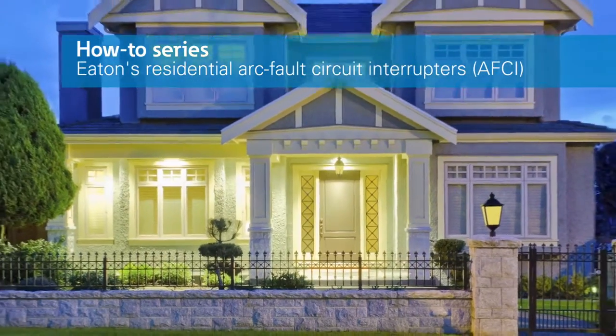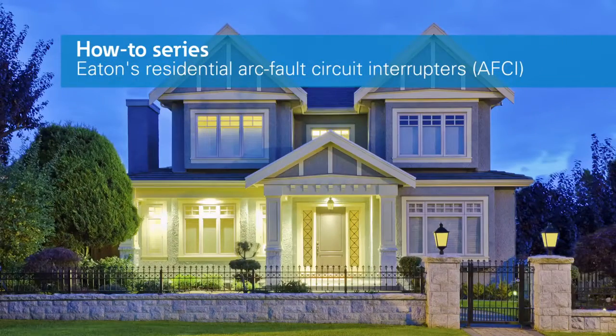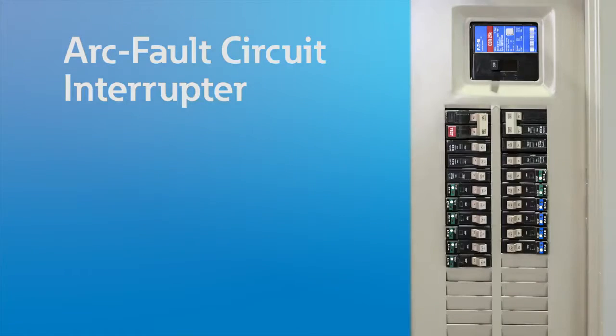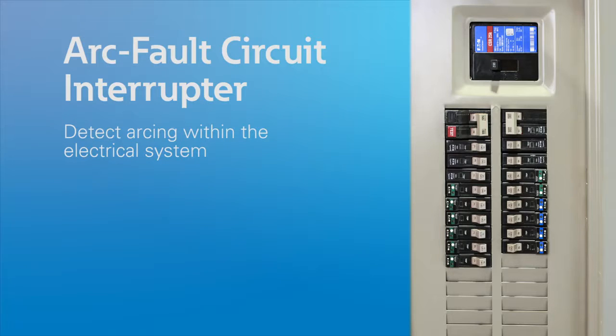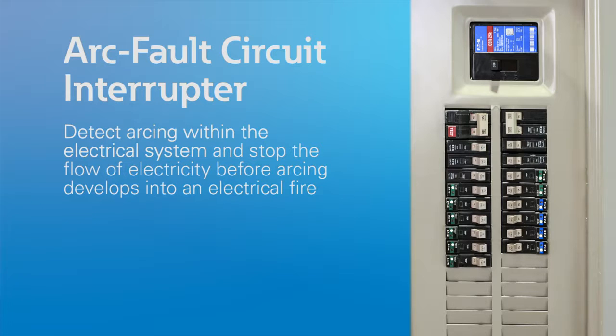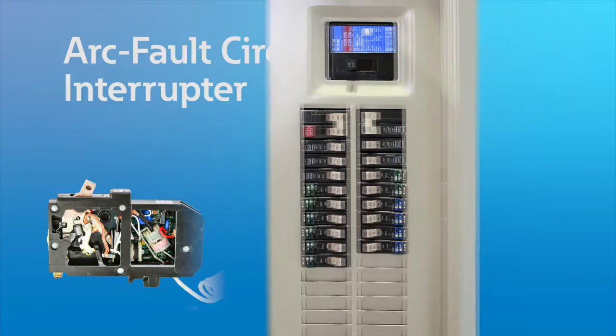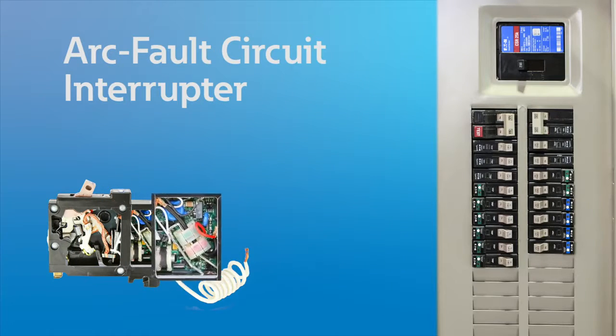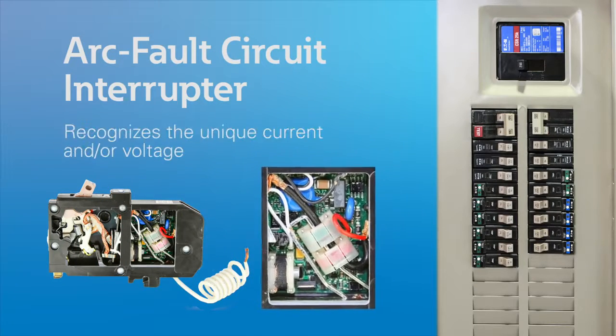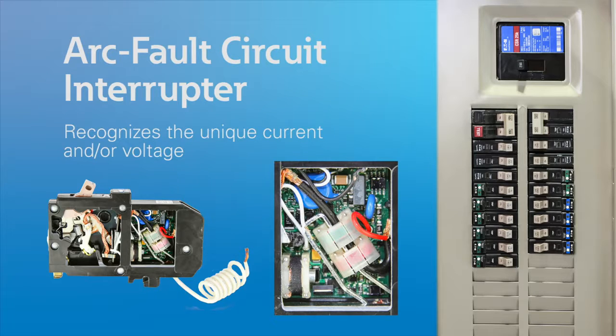Today's residential buildings have various types of devices that offer protection for the installed electrical system. One such device is an arc fault circuit interrupter, or AFCI. AFCIs are designed to detect arcing within the electrical system and stop the flow of electricity before the arcing develops into an electrical fire. The arc fault circuit interrupter is a circuit breaker with an integrated processor that recognizes the unique current and/or voltage signatures of arcing, which can cause electrical fires.